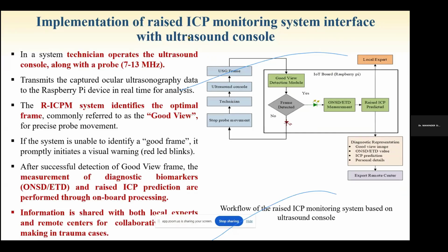Images are captured, and in real time, if our algorithm finds a good view frame, it highlights that the frame is detected and processes it for further measurement of ONSD and ETD, and calculates a ratio. Then we say whether the intracranial pressure is raised or not, and that information is passed to the local expert. This diagnostic representation also goes to remote centers through the cloud.